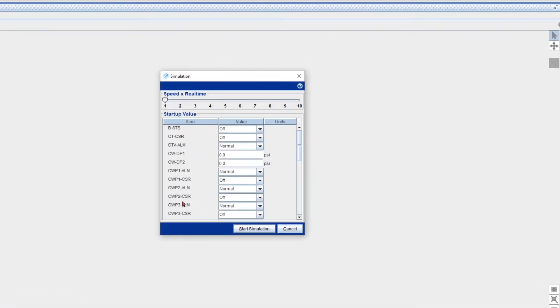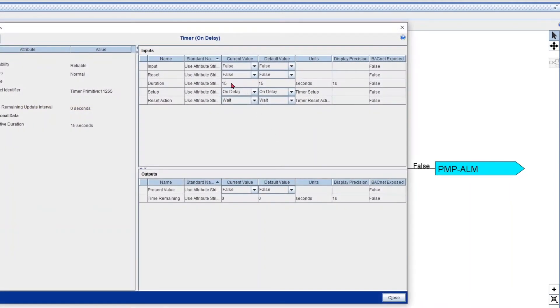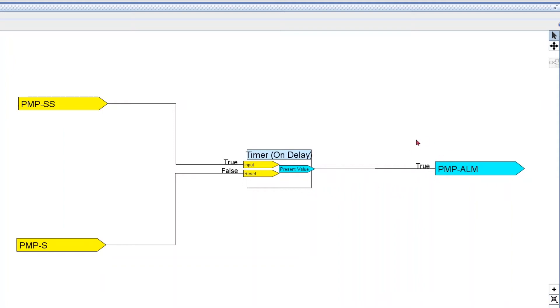I'm using boolean inputs and outputs, so you'll only see false and true instead of start, stop, status, alarm — but it's basically the same. Every time you give a true to the timer's input, it's gonna output a true after a time delay — that's why it's an on delay. That delay is the 15 seconds we set. So I'm gonna command my pump start-stop to true and send the command. After 15 seconds we're gonna get a true, which in this case means an alarm. There's a second part to this timer — let's just get the alarm first. We got a true after 15 seconds.